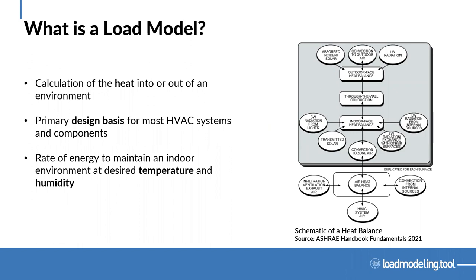Diving into our core topics for today — what is a load model? A load model is primarily the calculation of heat into or out of an environment. That could be an entire building or just one room, and the scale can slide based on what we need to do. It's also the primary design basis for our HVAC system, covering everything from a diffuser in a room all the way up to your central plant — chiller plant, cooling tower, all of those. All those pieces of equipment and interconnections first start as the results of a load model, so they're very fundamental to what we're doing.